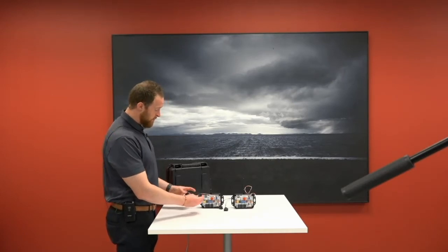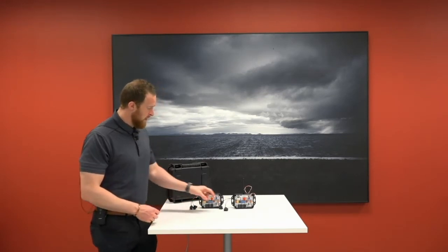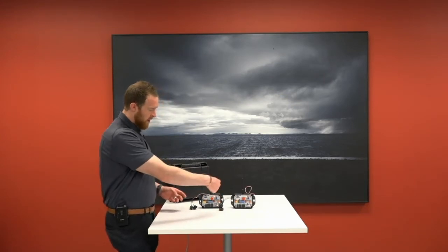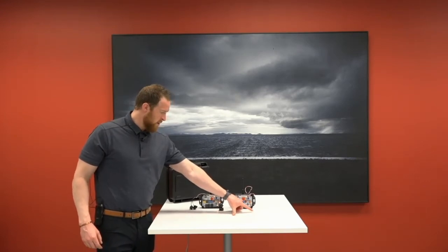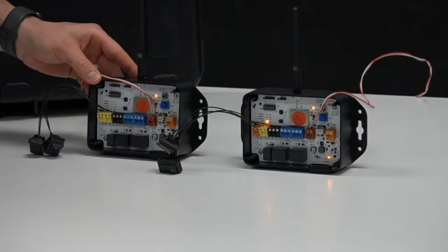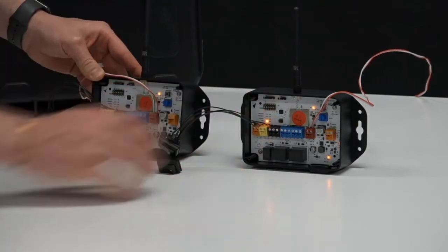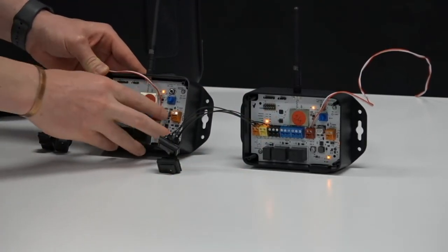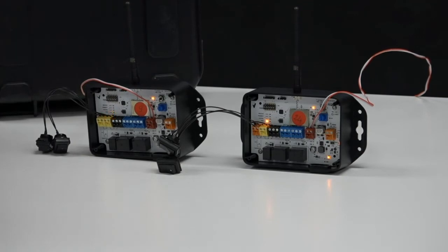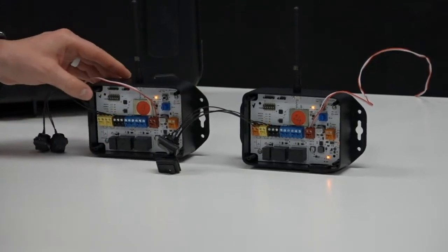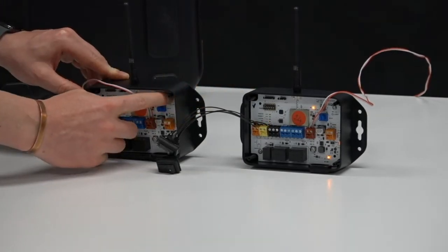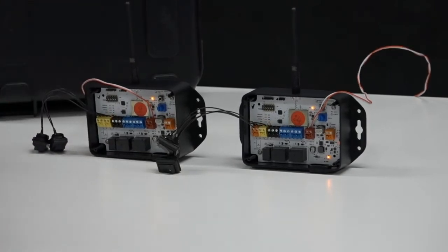That's why we've set up a little test scenario here where we've wired up just some toggle switches to our relay inputs on this device, and then toggle switches to our relay input on this device, and they're going to just be talking back and forth. You'll be able to see by an LED indicator which relay is triggered corresponding to the blue output terminal, relay output terminal. Just a quick reminder of these LED lights. You can see the run light on both of these is blinking orange. That means everything is normal, and we have our three orange LEDs on the right-hand side. That means everything with the power on this device is good. All of our dip switches are off because I pre-programmed these before this webinar, turning the dip switches, dip switch one on, dip switch one on, and pressing the program test button on one device. And it syncs them up, then I turn them off.